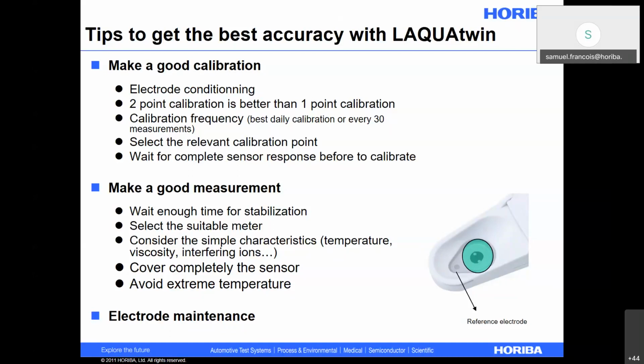And finally, we have the electrode maintenance. The electrode maintenance usually is the cleaning. There is not much to do, but it is mainly the cleaning with water after every measurement. I made the mistake myself too with my demo unit. Sometimes I do a sap measurement, and I forgot to remove it. And then when the sap dries on the sensor, it first gives a green color to the membrane. This usually doesn't affect the measurement so much. But if I have a small layer of dry organic material on the sensor, or a thin layer of grease, this is affecting my measurement. The best is to clean the electrode after every measurement.